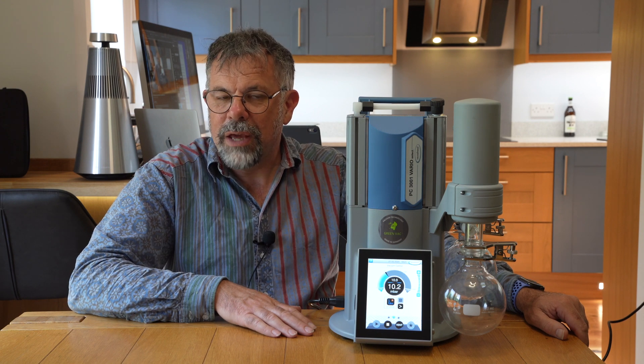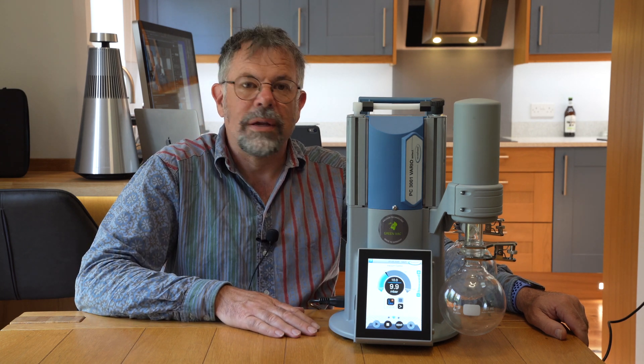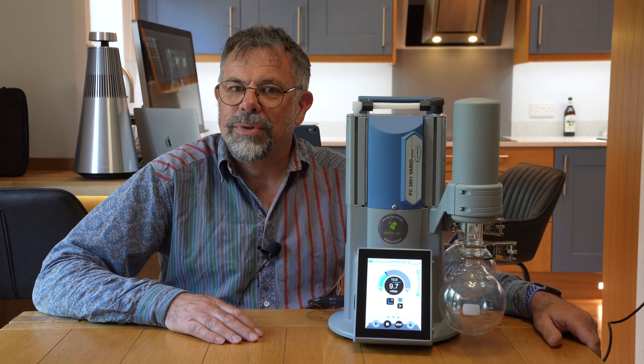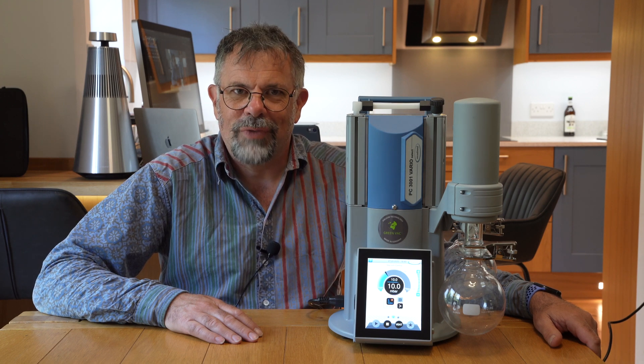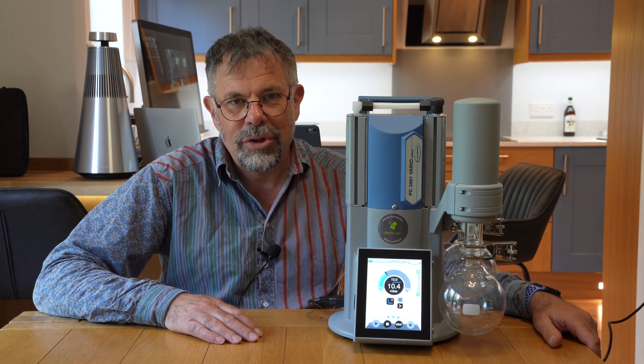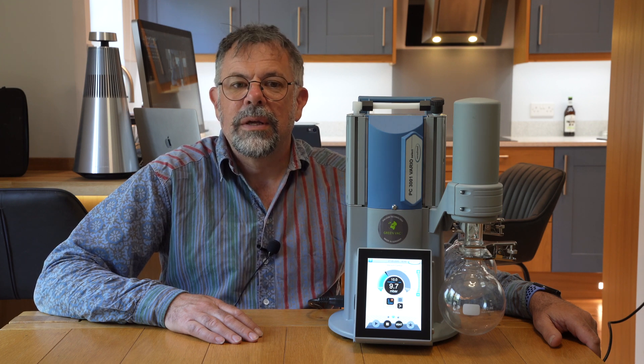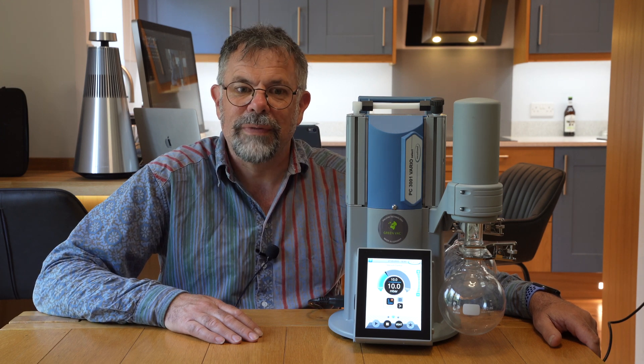No bumping, no foaming issues with your rotary evaporator. Add this to any quality rotary evaporator and you will have the best evaporation system you can possibly have in your fume hood. So what does Vario mean? Many vacuum pumps run at a constant motor speed with the pistons working at a constant rate and the vacuum is controlled by a valve. Now that's both inefficient, wears the components out quickly, and having a valve means the pressure can fluctuate quite considerably — thereby you can end up with foaming and bumping, hence those sort of things happening in the past with rotary evaporators.